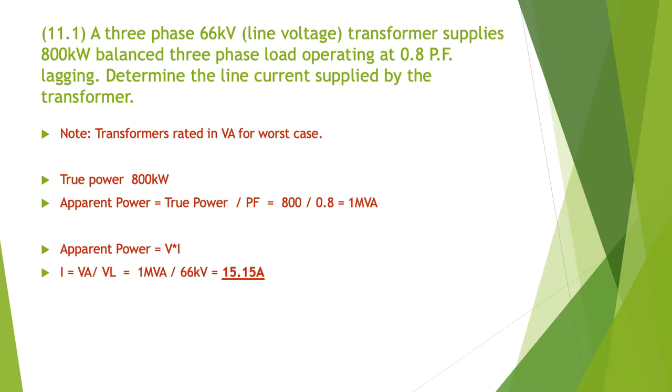They've given us the voltage, so our one MVA divided by 66 kV comes out at 15.15 amps.